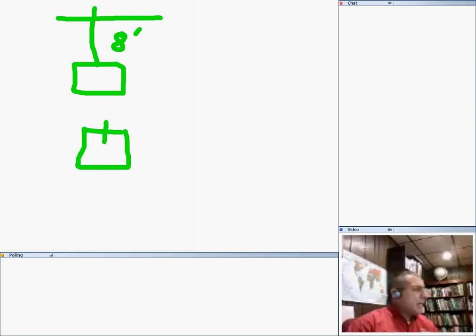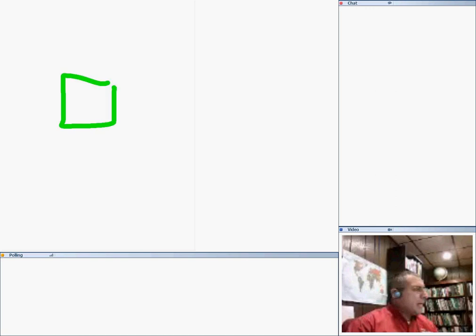If you have a non-metallic box, guys, there are no clamps. So like my NM cable, you have to support the NM cable, guys, every 8 inches if there's no clamp. Here's my NM cable, and I have a clamp here. I have a clamp. Then you can support it from here to here. So here's the clamp, here's my clamp over here. I can go all the way to 12 inches. So that's the point, guys. If you have a clamp, 12 inches. If you don't have a clamp, 8 inches. And I guarantee you it will be on your exam.